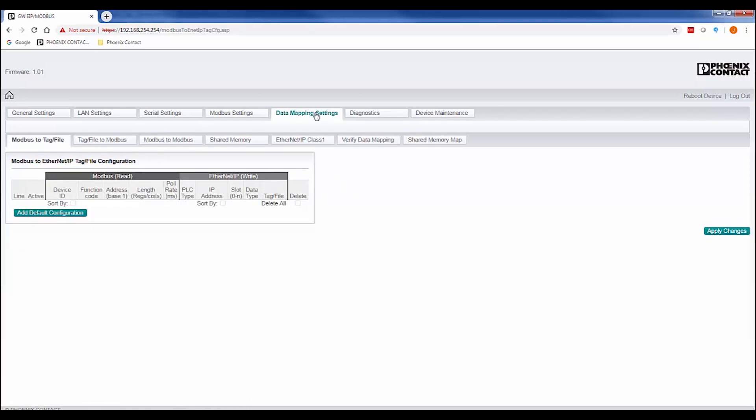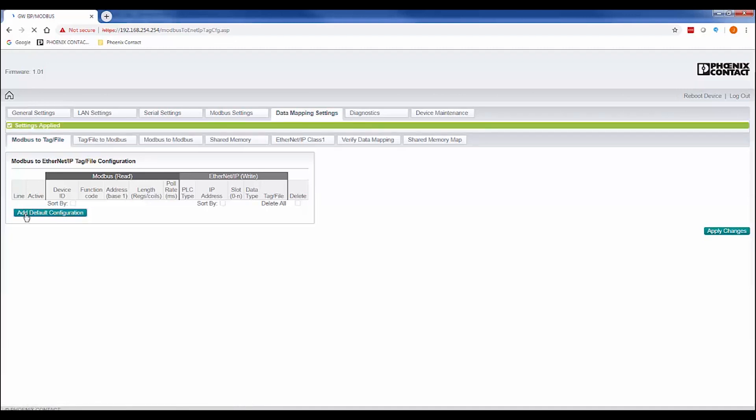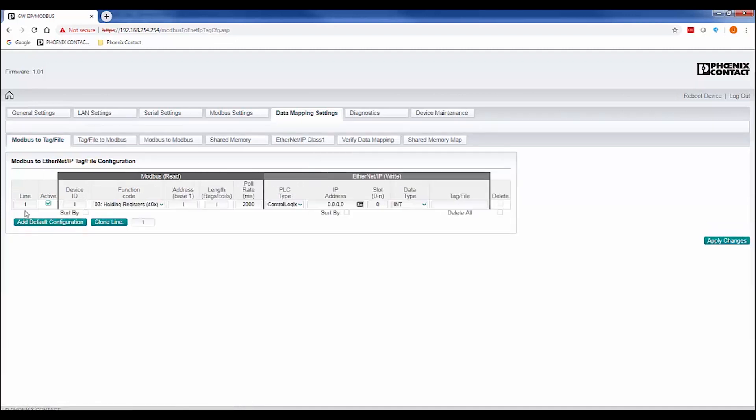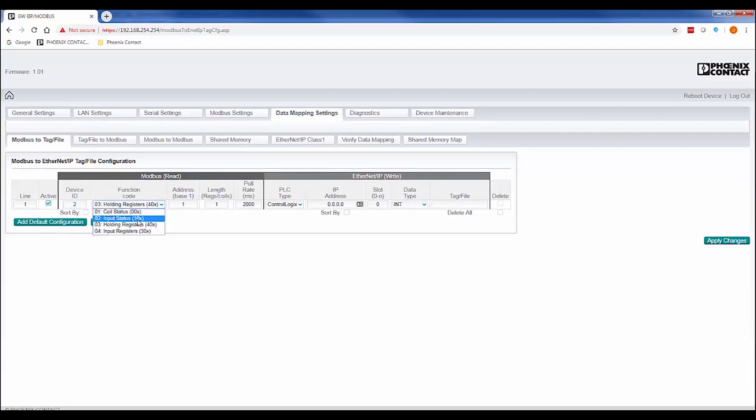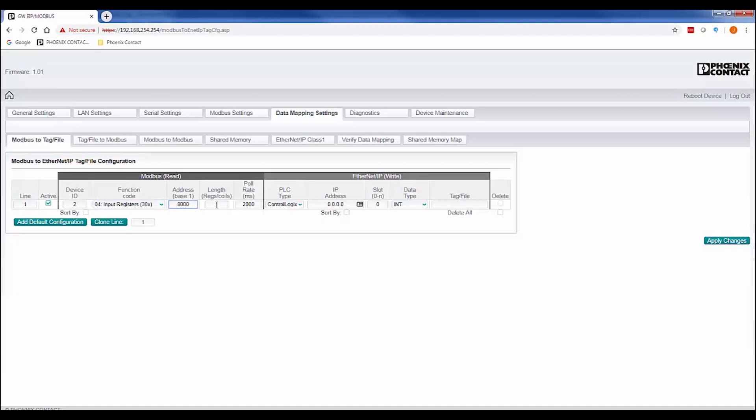Access the Modbus to tag file tab to set up a Modbus read that will then transfer to the PLC. Click the Add Default Configuration button to set up a read from our Modbus RTU device. First enter the device ID of our serial device, the function code for the Modbus read request, along with the address and length of the read.